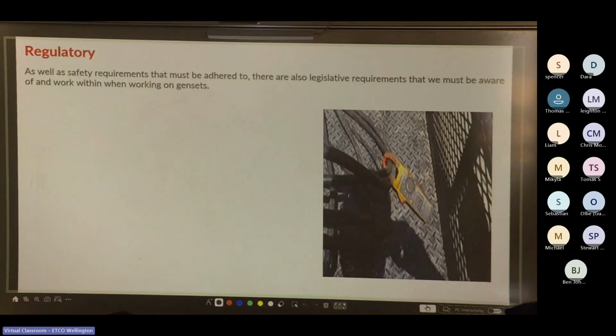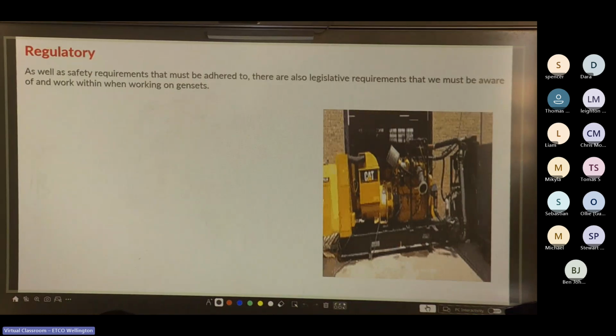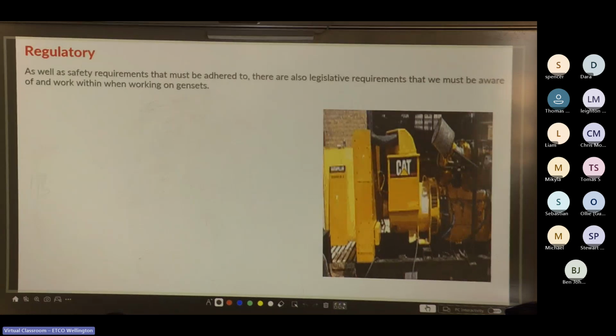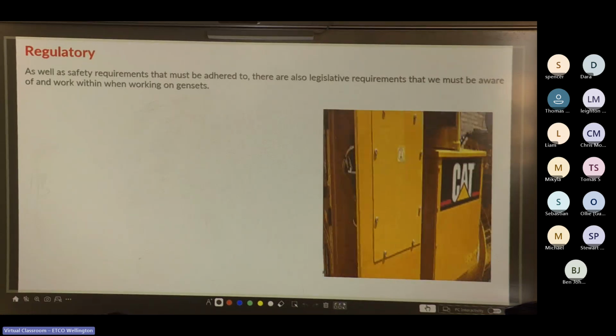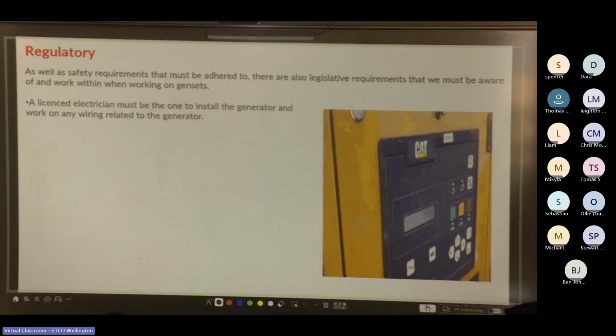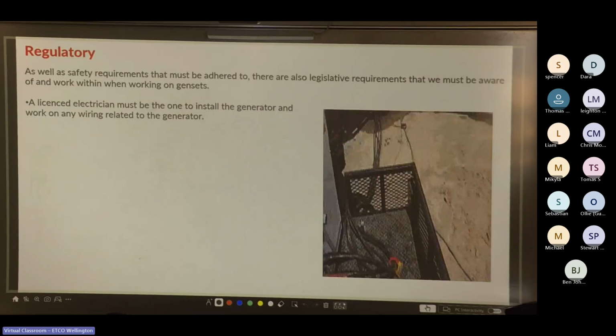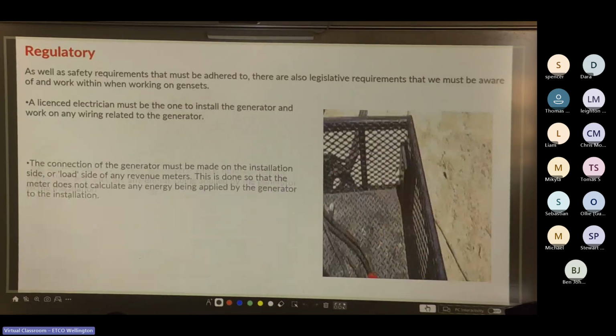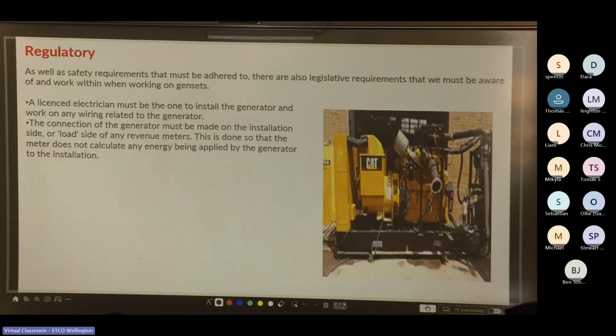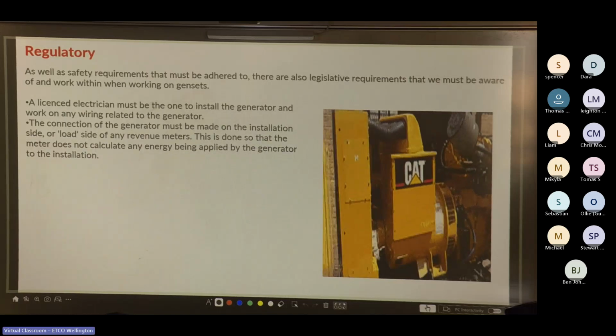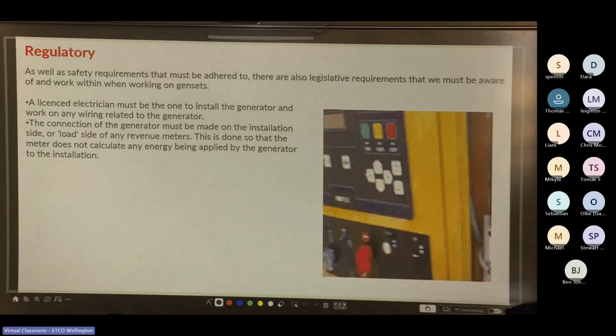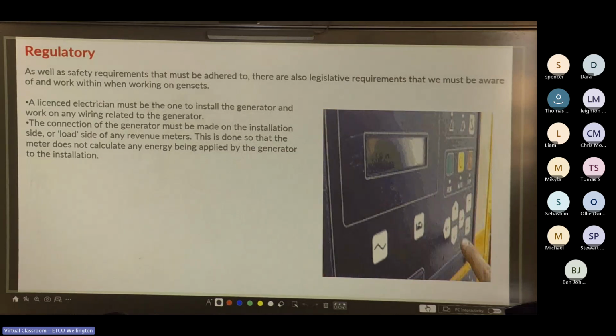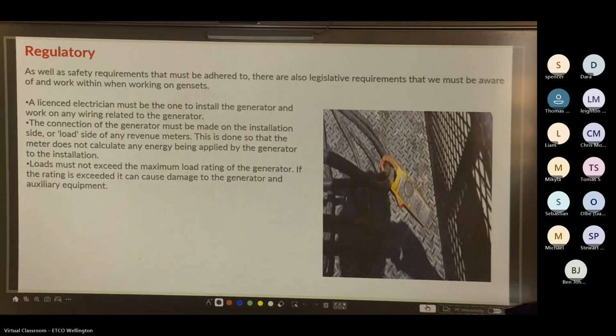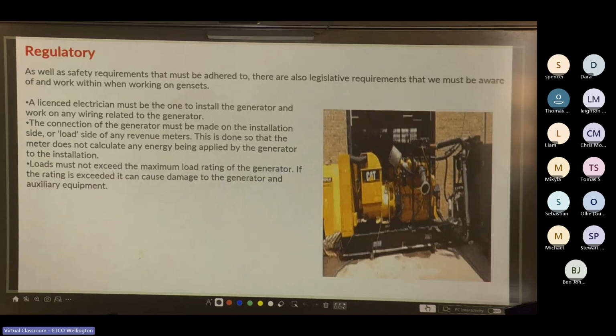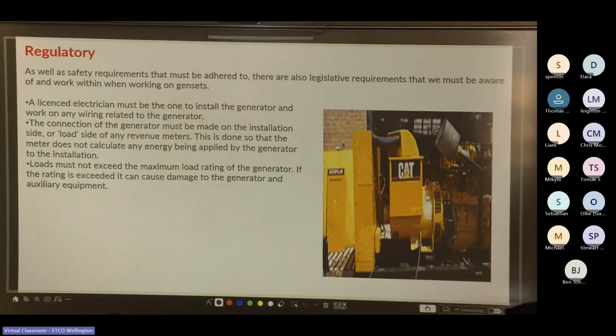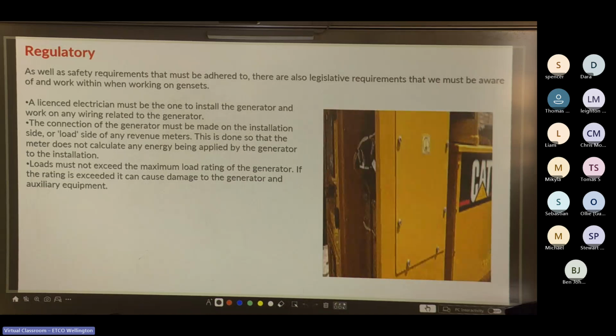Cool. So as well as regulatory and safety requirements to be adhered to, there are also legislative requirements that we must be aware of and work within when working on gensets. A licensed electrician must be the one to install the generator and work on any wiring related to the generator. The connection of the generator must be made on the installation side or load side of any revenue meters. This is done so that the meter does not calculate any energy being applied by the generator to the installation. Loads must not exceed the maximum load rating of the generator. If the load rating is exceeded, it can cause damage to the generator and auxiliary equipment.